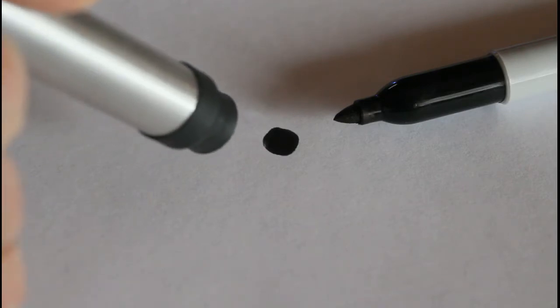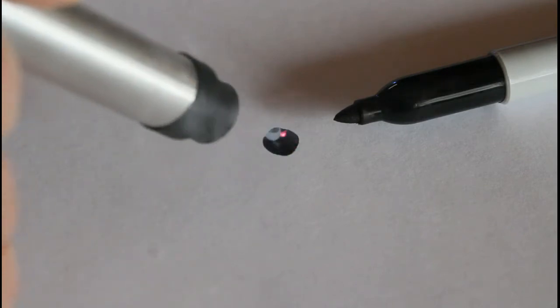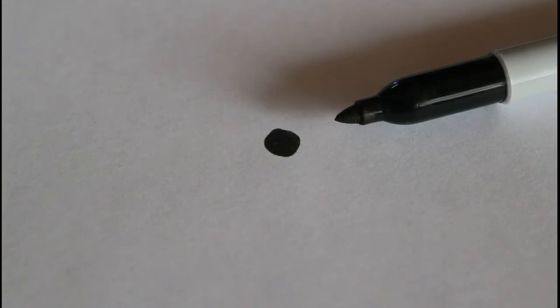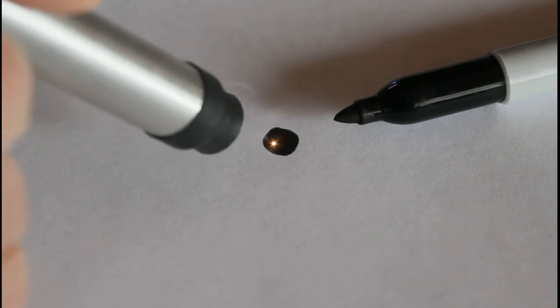To be effective, the tip of the handpiece, which contains a constant wave diode laser and precision optical elements, must be held the correct distance from the surface of the skin to form a distinct pinpoint of light. As you can see in this video, when the beam is properly focused on a dark target, such as the melanin in a hair follicle, especially if treated with carbon dye, the target absorbs the light energy and it is converted to heat.